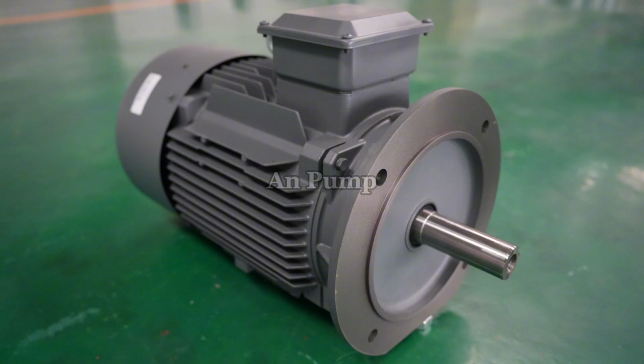That means using the wrong frequency can overload the motor and damage the pump. For example, a pump designed for 50 Hz may consume significantly more power when operated at 60 Hz. Incorrect frequency can lead to overheating, excessive vibration, bearing damage, and even cavitation. This is especially important for export projects. Different countries use different electrical standards, so frequency must always be confirmed before production and installation. Whenever possible, dual-frequency motors are a good solution for international projects.